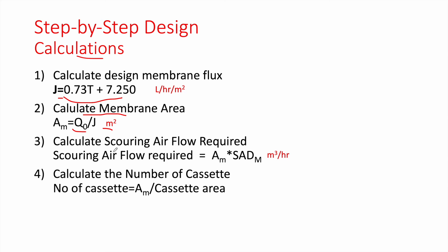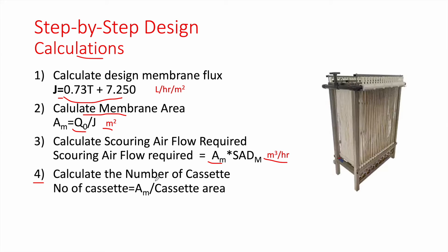Step 3: Calculate the scouring airflow required by the MBR modules — equal to AM times SAD (0.3), giving a value in cubic meters per hour of air injected through coarse bubble diffusers by blowers. Step 4: Calculate the number of cassettes by dividing the total membrane area by the area per cassette, which you obtain from the manufacturer.